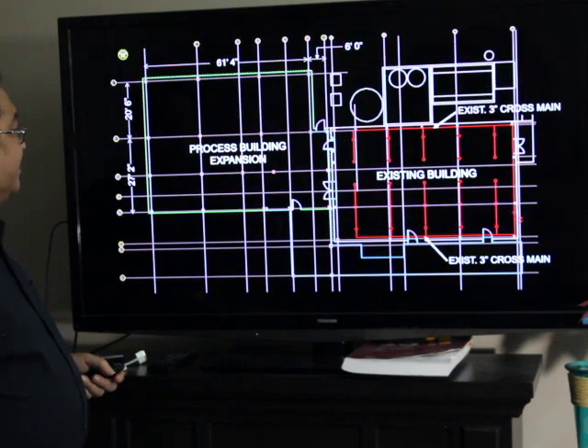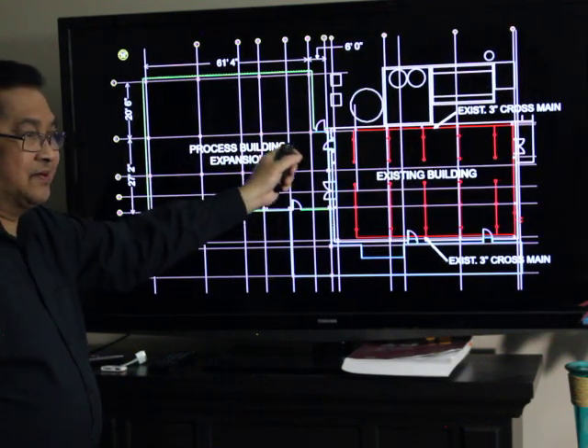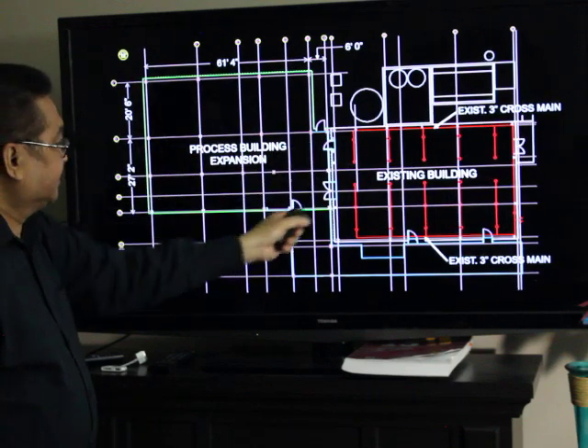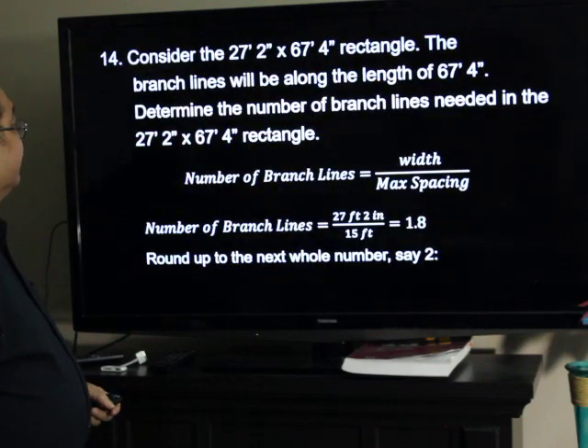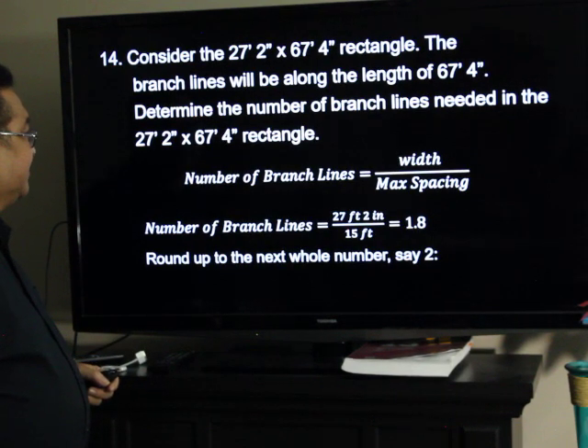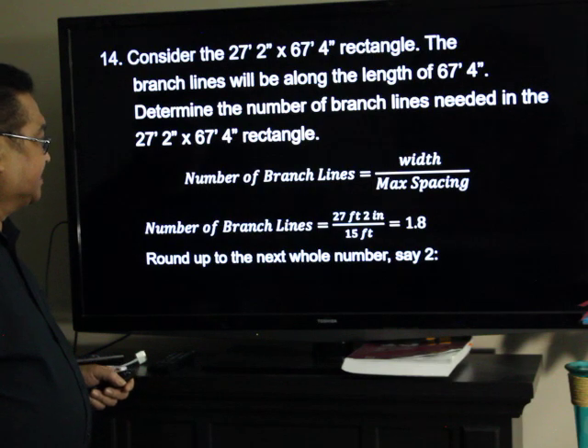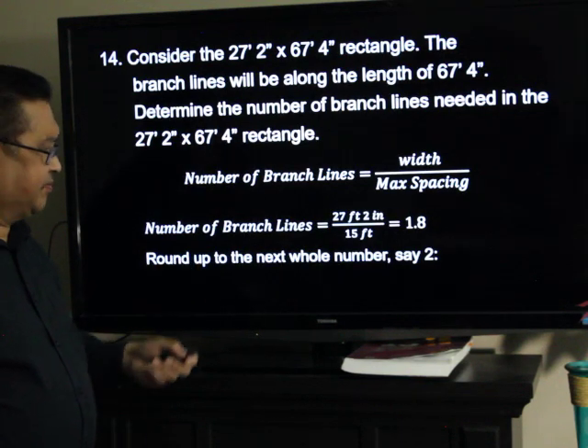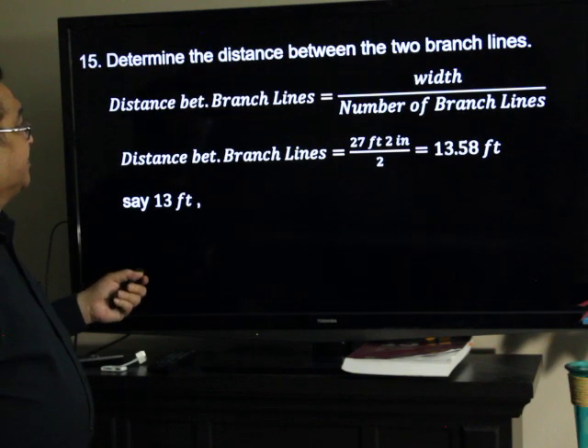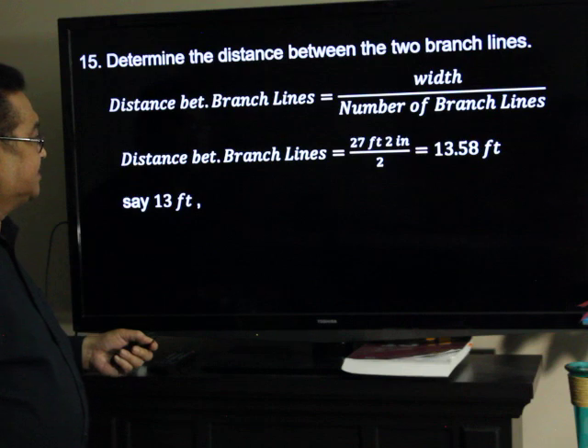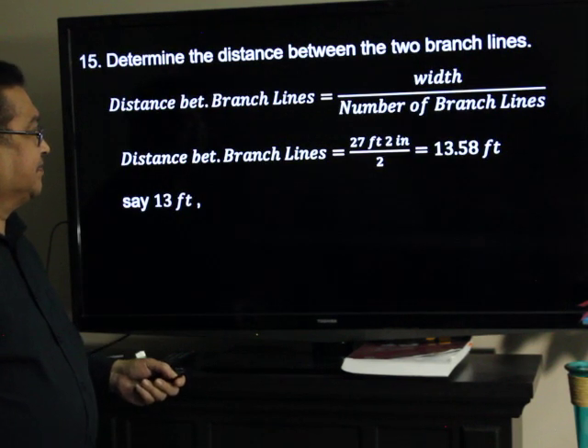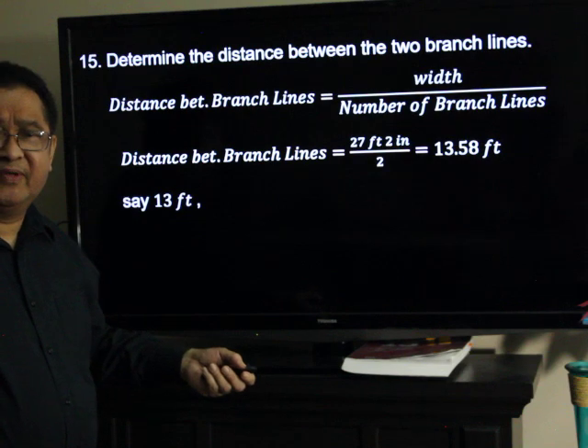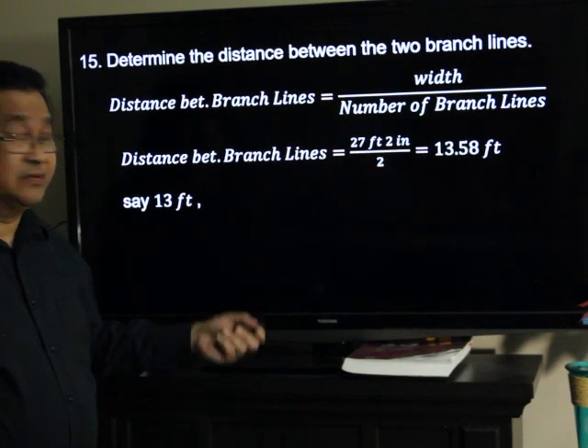Now, we go to the next rectangle, the lower one, which is 27 feet 2 inches by 67 feet 4 inches. Determine the number of branch lines needed in the rectangle: the width divided by the maximum spacing — 27 feet 2 inches divided by 15 — we have 1.8. Round up to the next whole number: 2. Determine the distance between two branch lines: the width divided by 2, so 27 feet 2 inches divided by 2 — 13.58, let's say 13 feet — which doesn't exceed 15 feet and is more than 6 feet, so it's okay for now.